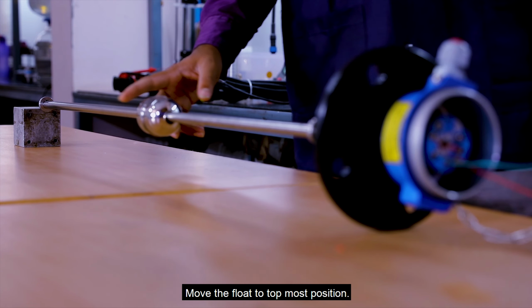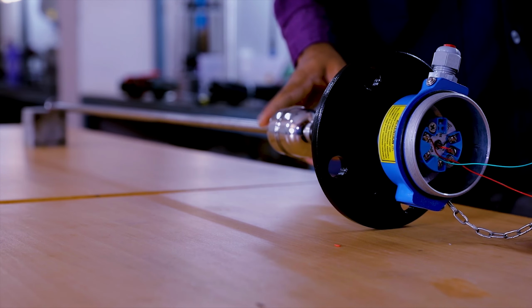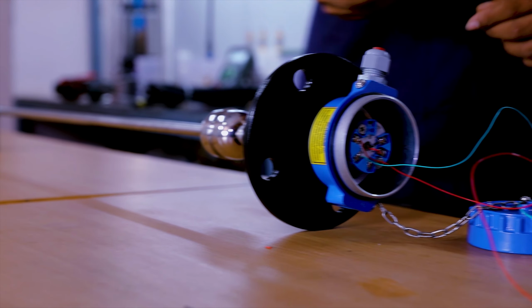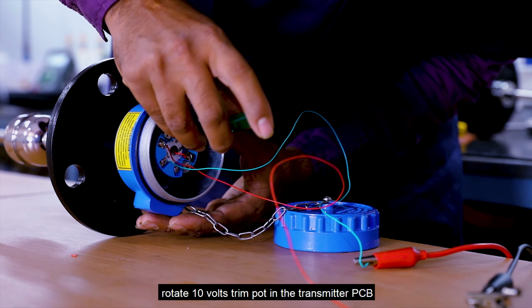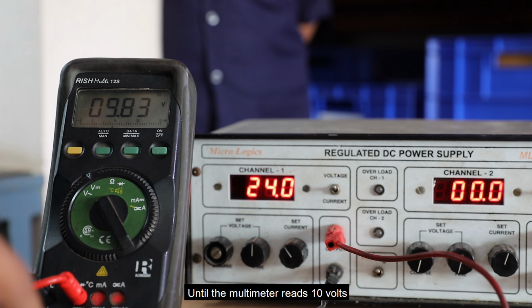Move the float to the topmost position. To set 10 volts, rotate the 10 volts trim pot in the transmitter PCB until the multimeter reads 10 volts. Now the calibration is completed successfully.